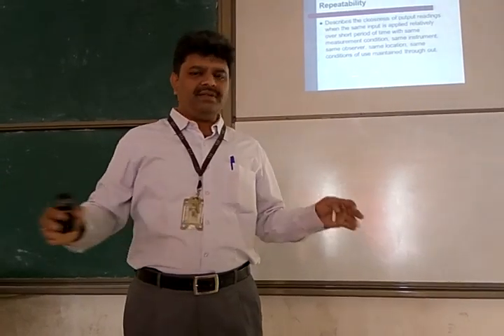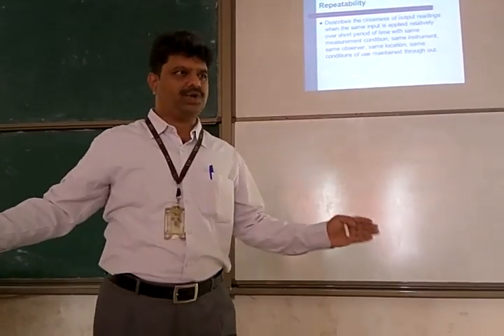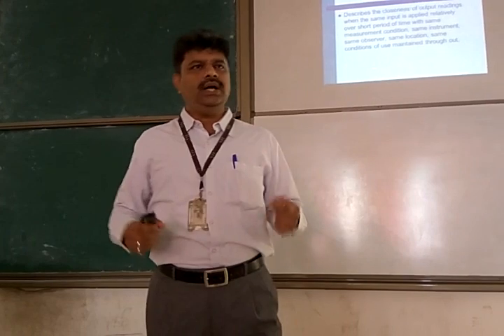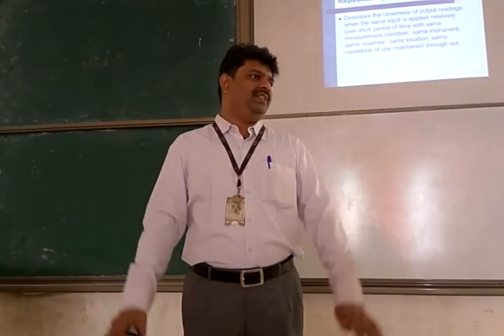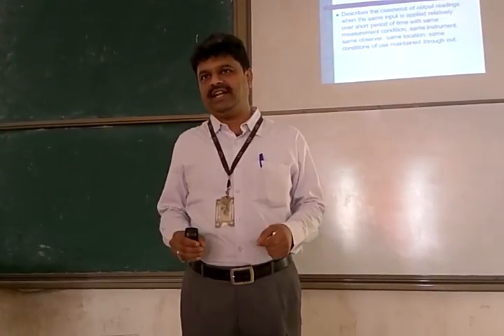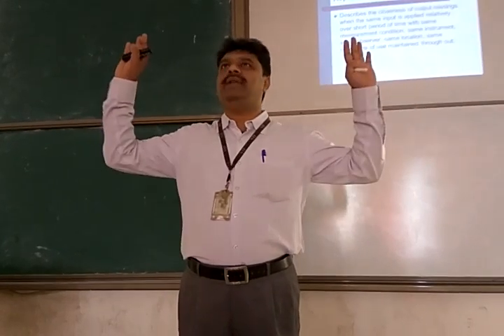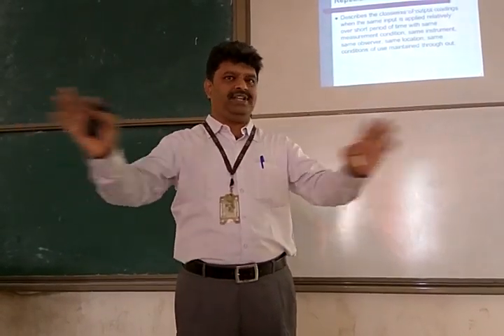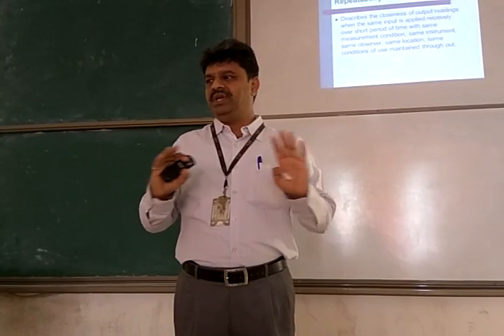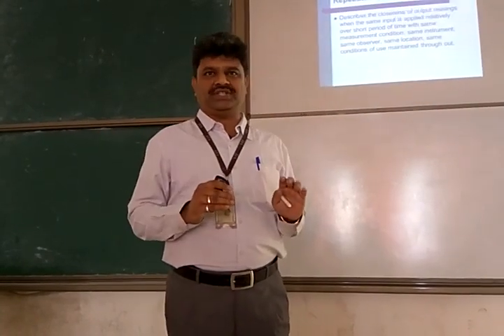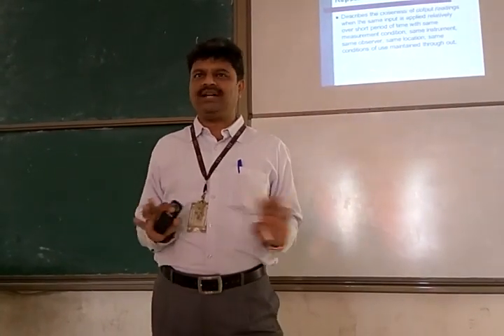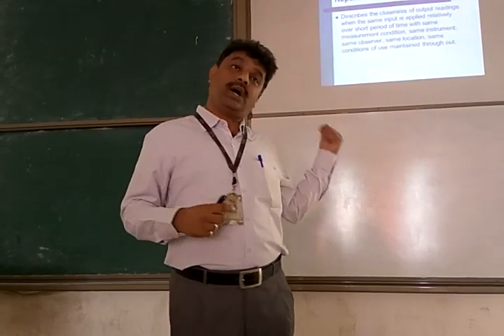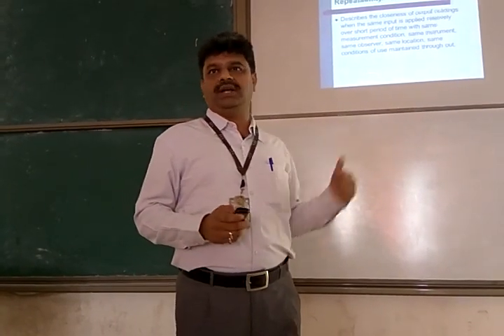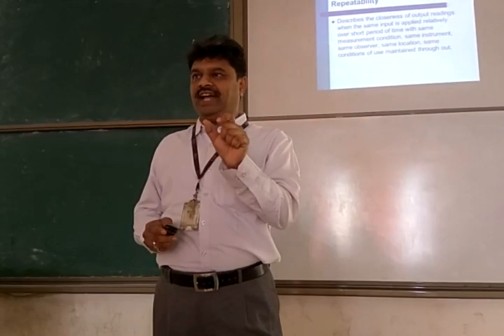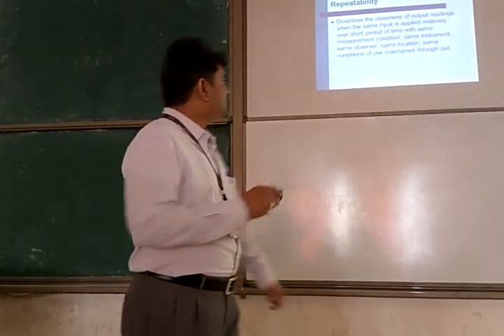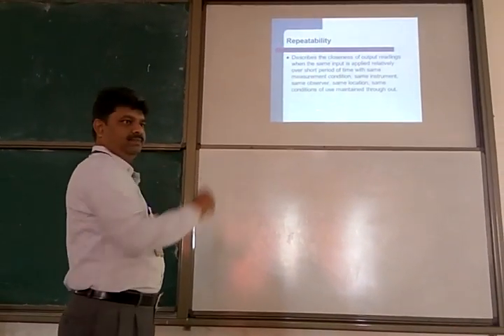I take measurement in a short period of time, say half an hour or an hour. Same observer performing the experiment and taking the reading. Same instrument, same lighting, same temperature, same humidity—no environmental condition changes, the observer doesn't change, the instrument doesn't change. Take the reading and compute the precision in a short period of time. Then I call this term repeatability.